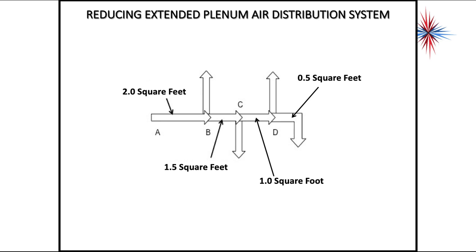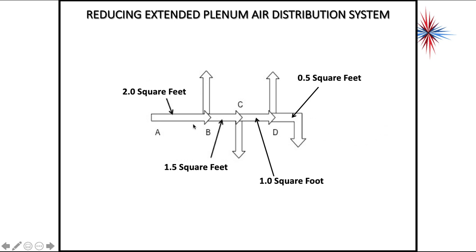If you have too little velocity, you'll start seeing dust and dirt buildup in the ductwork. Also, sometimes you won't be able to reach the far corners of the room the air is blowing into, and the air will feel stagnant. So, extended plenum systems come in two different types: the standard width, which is all one size — you lose velocity near the end — and the reducing extended plenum system, which is more expensive to install, but does a better job of maintaining velocity all the way down. And that takes care of the reducing extended plenum system.